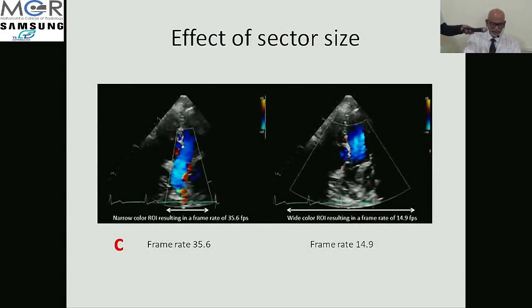Just an example: here the frame rate is 35.6, here the frame rate is 14.9. Here the depth is more, here the depth is less. You can see the whole flow here, but here the flow is cut. There is no flow seen beyond this. So the completeness is there in this frame, but not in this frame. This is the effect of the sector size. One size has covered the whole frame, and the other size is restricted to this much only. So this has increased the frame rate.